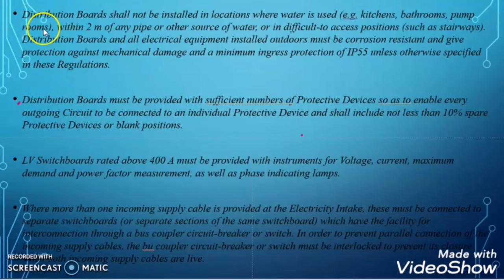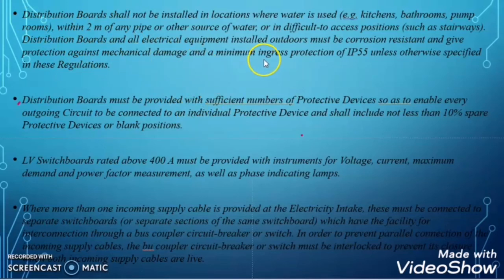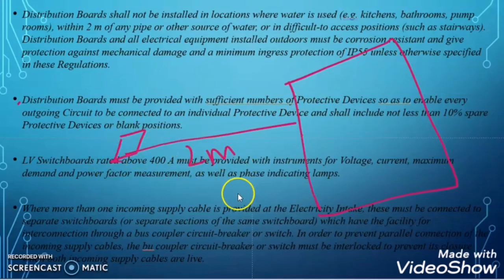The next clause states that distribution boards shall not be installed in locations where water is used — like kitchens, bathrooms, or pump rooms — and must be at least 2 meters from any pipe or other source of water, or in difficult-to-access positions such as staircases. Distribution boards and all electrical equipment installed outdoors must be corrosion resistant, protected against mechanical damage, and have a minimum ingress protection rating of IP55 unless otherwise specified.